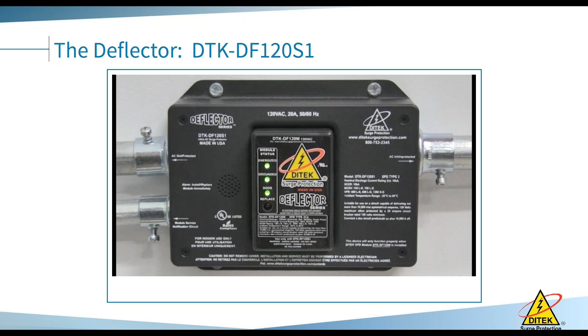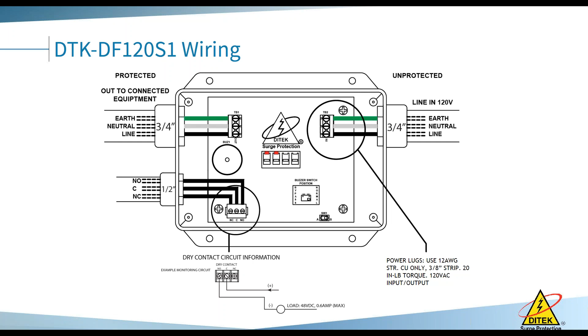Obviously this is underneath it. We've got a dry contact terminal there, and this does have an audible alarm that you can disengage. If you notice that buzzer switch position on the bottom right, if you do turn the alarm off, just to silence it, you can't put a good module in there without the alarm going back on. So basically you're going to have to take the cap off and reset it back to normal. If you do turn this off, it will not behave properly. You have to put it back to normal and have a good module in for that alarm to go off.